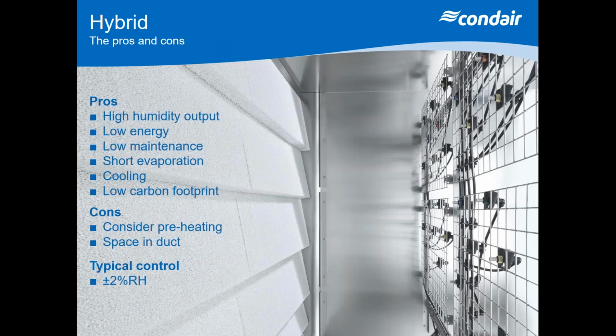So moving on now to a hybrid system. Now, some of you may have never seen this before, but this is a system that's going to give you the best control with the lowest energy in the marketplace. How we do it is a combination of the two systems you've already seen. With this system, rather than using high pressure spray, you're using low pressure spray. So there's less energy consumption on the pump. You're running around 10 bar, and you have multiples of very small outputs of nozzle to give you the duties you need.